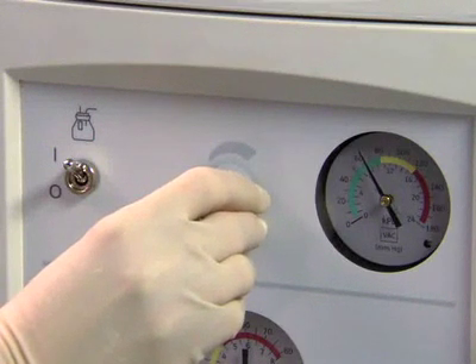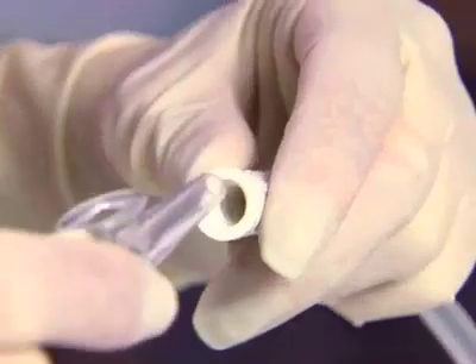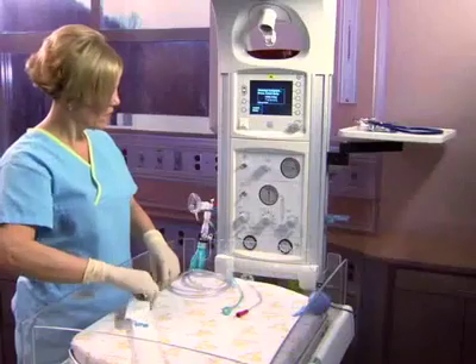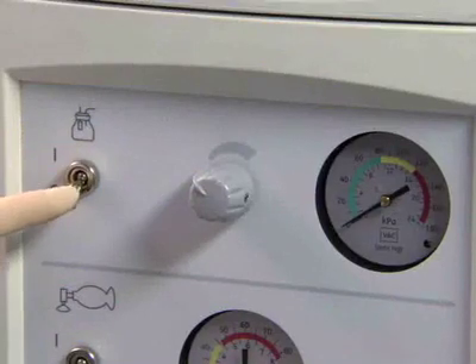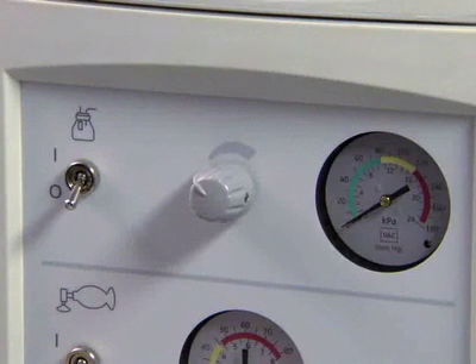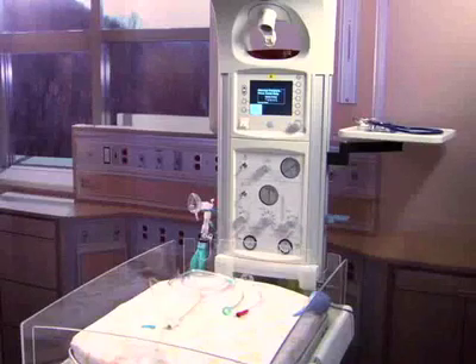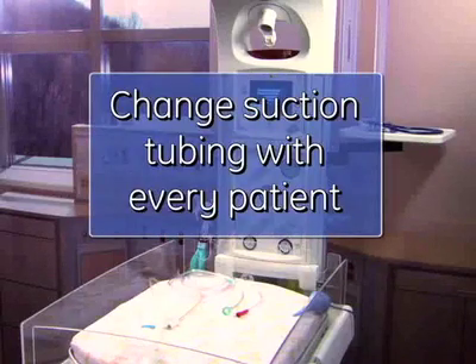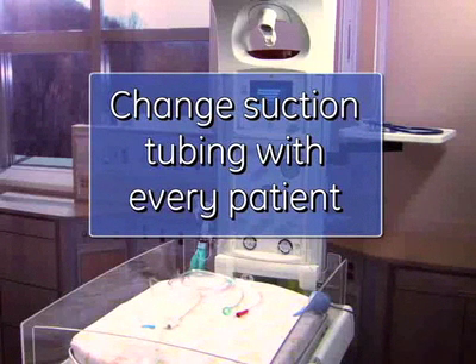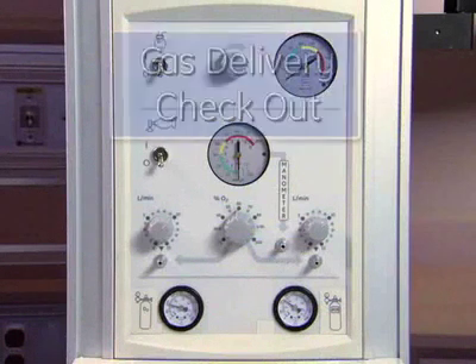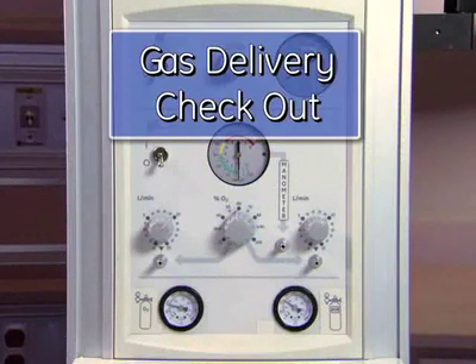Once you have set the desired vacuum level, attach the suction catheter or meconium aspirator of your choice. Turn the suction control switch off until ready to initiate resuscitation or airway support measures to avoid wasting gas. Suction tubing between the canister and the patient should be changed with every patient. Next, you will need to check out the bag and mask gas delivery system.